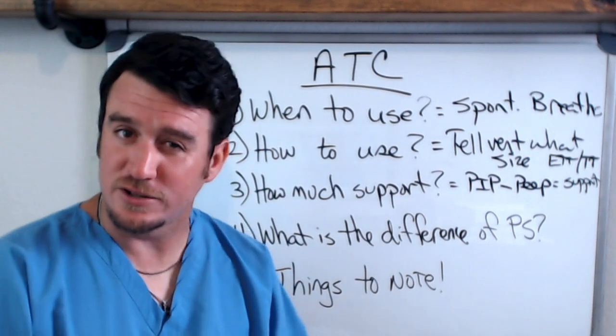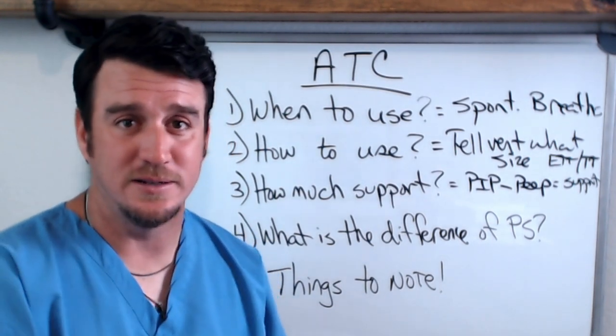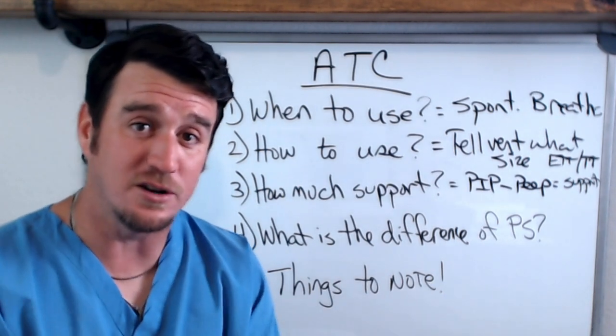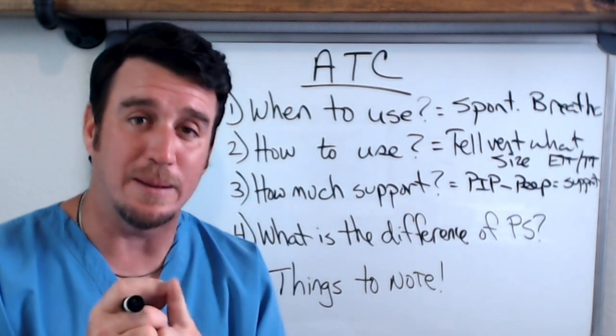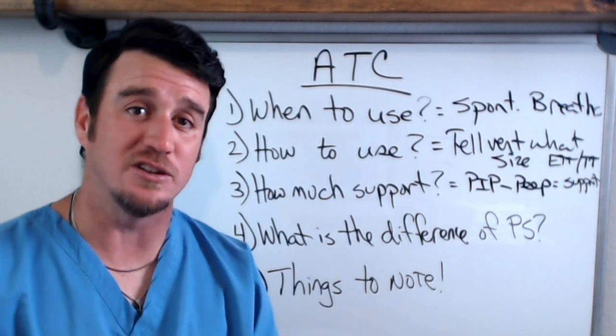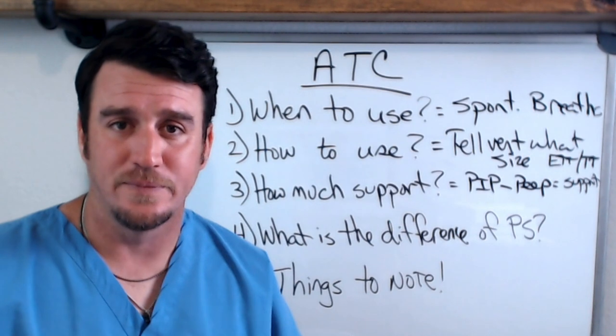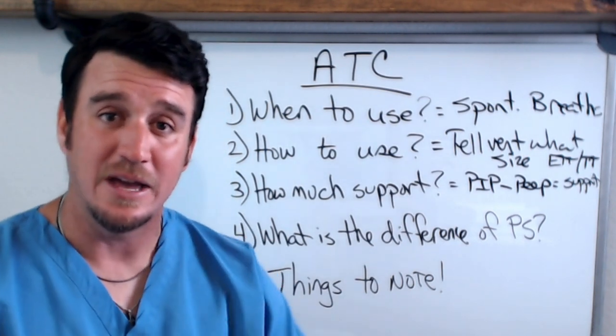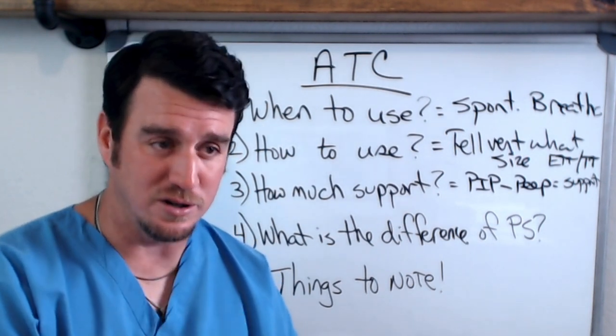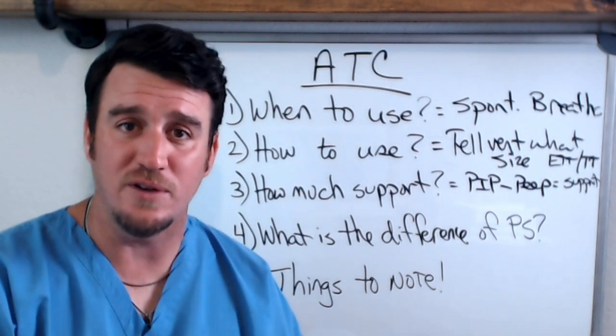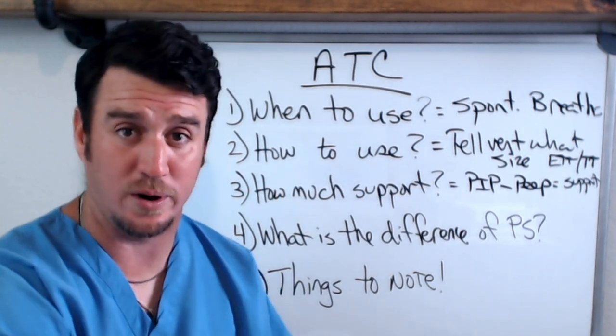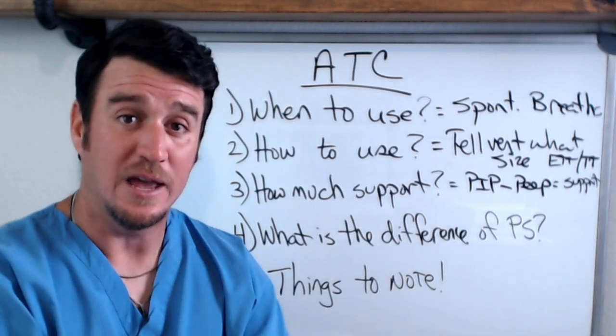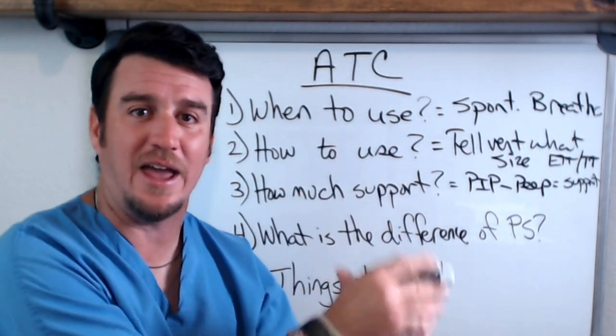This is what I'm trying to get you to understand. You can make your patients look good, but you're creating a false positive image of how the patient is doing if you have your AAC or ATC and your pressure support activated at the same time. You should have one or the other if your vent allows you to have both simultaneously. If you're working with the Bennetts, this is not a problem — you can only have one or the other. But other vents may allow both activated at the same time, and you need to educate your staff: if you have pressure support dialed in to augment spontaneous tidal volume, then the AAC or ATC needs to be turned off. If you're not going to use pressure support, then turn the ATC or AAC on.